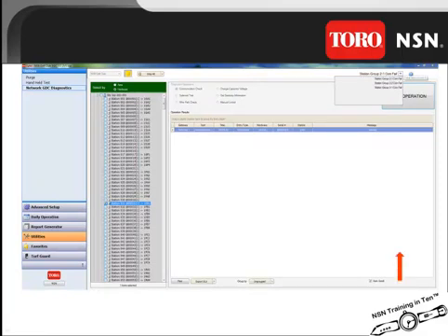If the failure is only that of a station, check the decoder and its wire connectors. If it is a larger communication failure, first check the gateway and daughter boards. If they are functioning properly, do a wire path check that we will cover later.